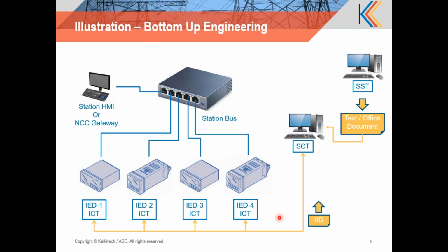Now this file is imported into the SCT, where the SCT can merge that information. It can resolve all the information there and generate an SCD file. Now the difference here is that this SCD file that is generated is not really needed. It's not necessary to take this back to the ICTs to configure the devices because that is already done.